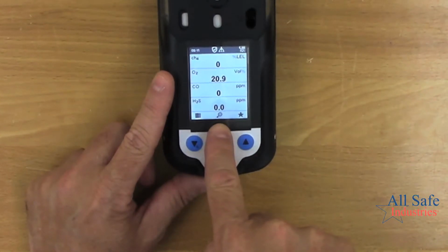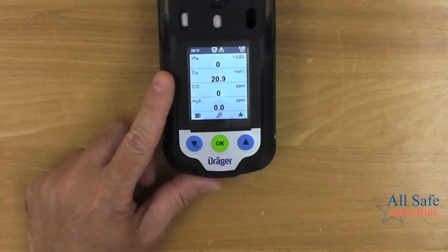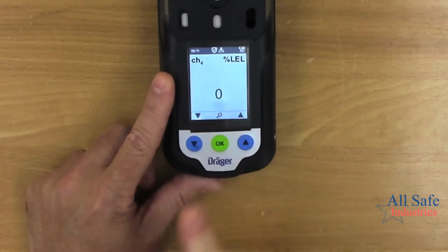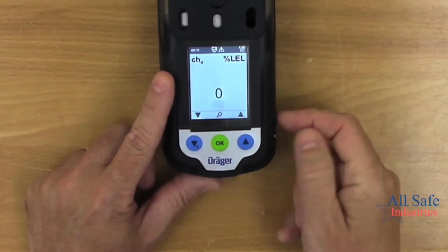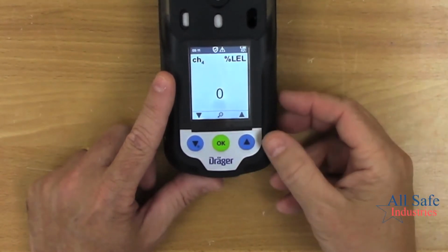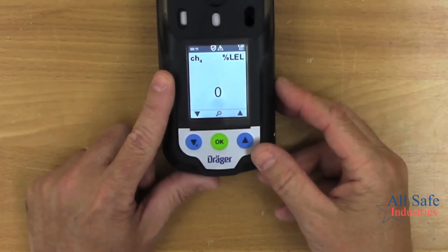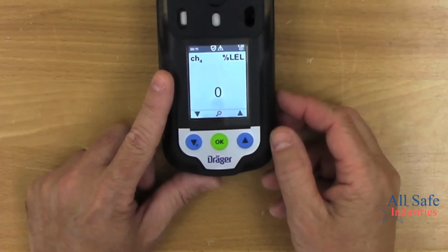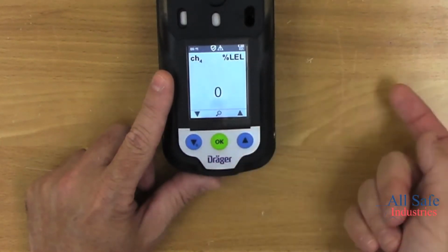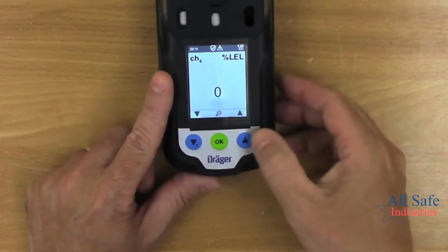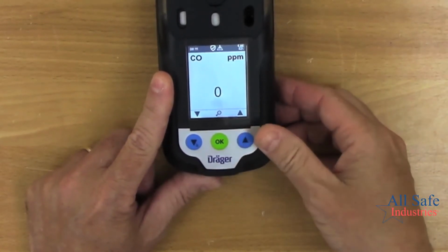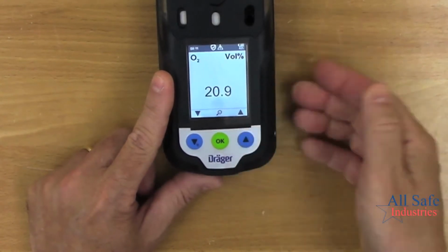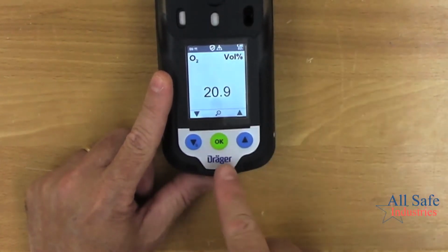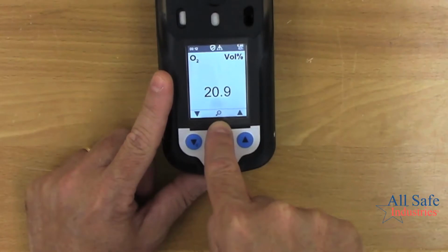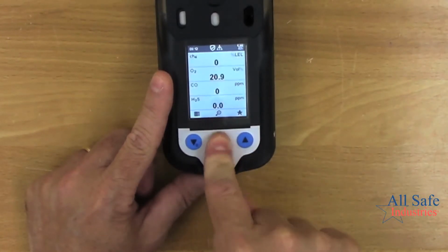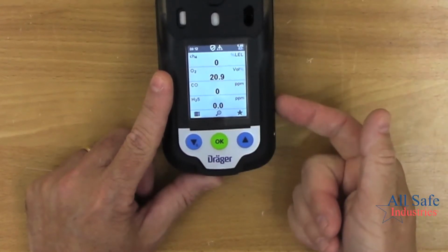Notice how it lines up with the little magnifying glass with the plus sign in the middle. By pushing that button, I get to zoom into the individual channels. So if I'm looking through a full face mask, or in a level A suit and having trouble reading the small characters, I can use this zoom-in function, and my up and down buttons scroll through the different channels or sensors installed in my unit. Once I've seen what I need, that becomes a magnifying glass with a minus sign. If I press it again, I go back to seeing all the information on one screen.